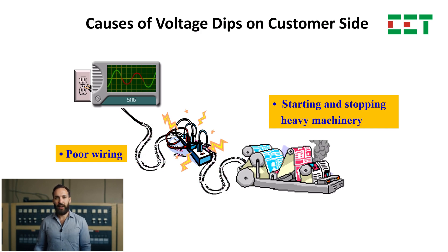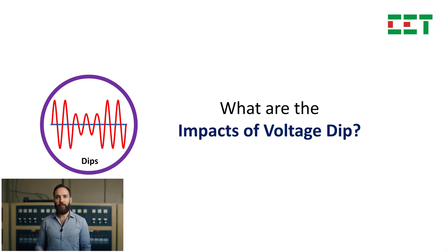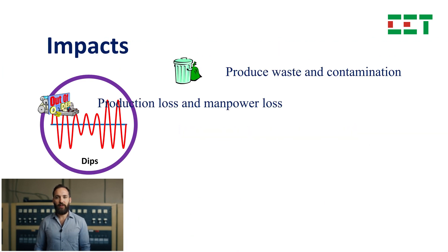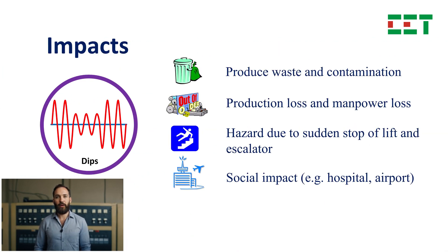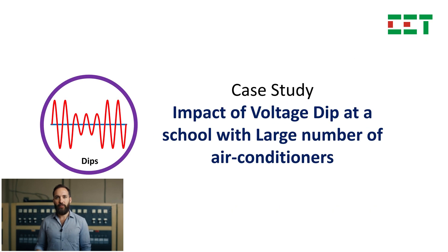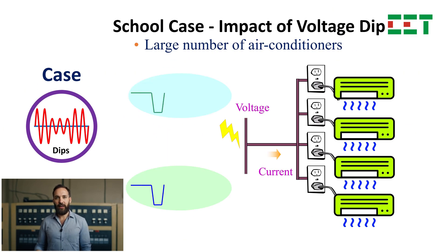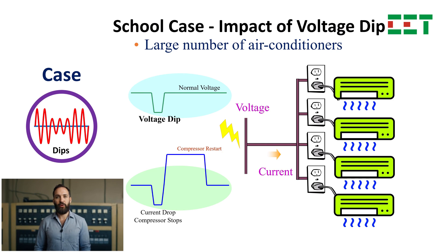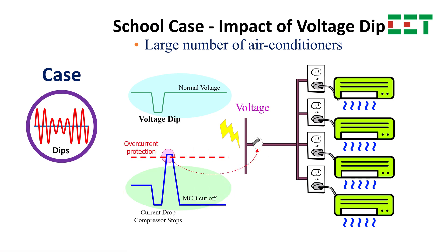Voltage dips can affect connected equipment, causing sensitive circuits or MCBs to trip, leading to operational stoppages. For example, voltage dips in high-rise buildings during heavy air conditioner use can cause overcurrent and MCB trips, resulting in blackouts.